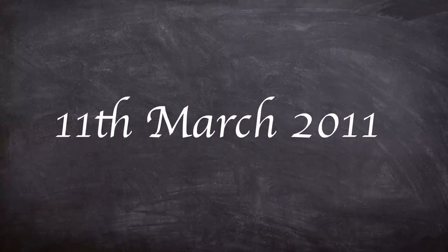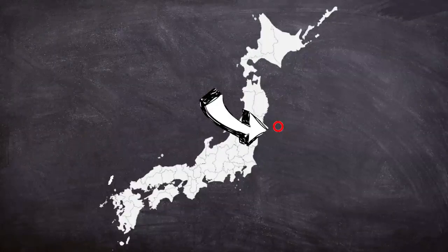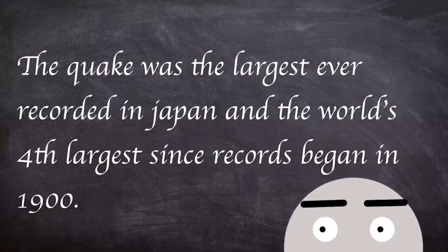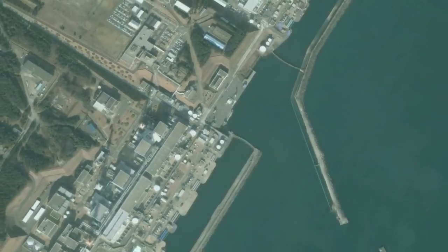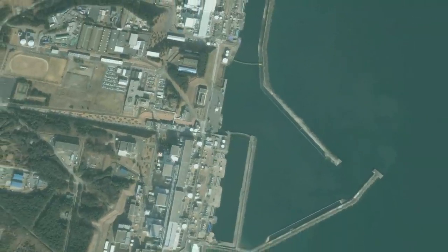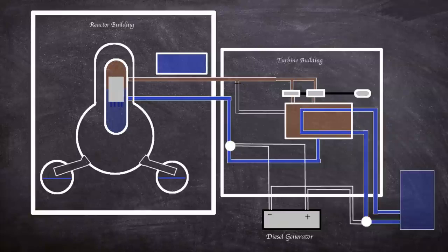On the 11th of March, at 14:46 local time, an earthquake of a magnitude of nine lasted for two minutes. It was caused by a sudden release of energy at the interface where the Pacific tectonic plate forces its way under the North American plate. The earthquake was the largest ever recorded in Japan and the world's fourth largest since records began in 1900. At the time of the earthquake, sensors at the plant detected ground movement and initiated a scram in the three operating reactors. This was built into the design of the plant and the action controlled the reactor's reactivity.